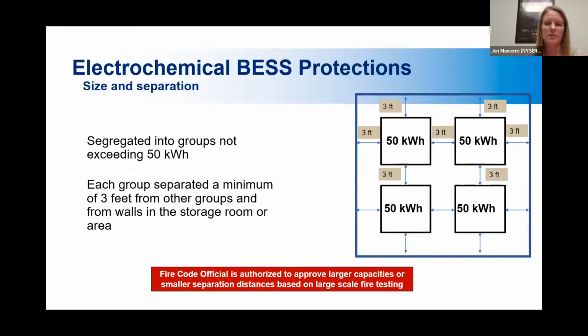This example, I already alluded to a little bit here. So for any of the larger energy storage systems, the fire code requires that they be in blocks of batteries, no more than 50 kilowatt hours per block. And each of those blocks needs to be spaced at least 3 feet apart from each other and also from the walls, as you can see in the diagram here.